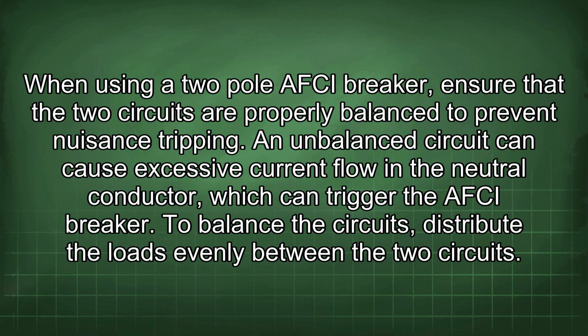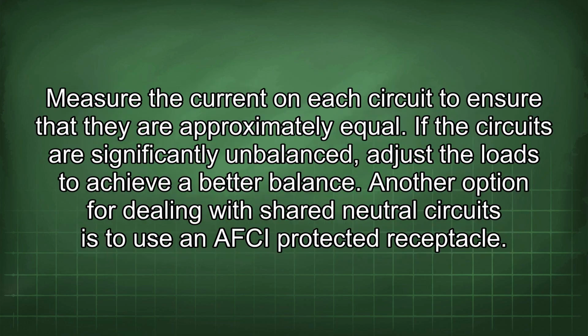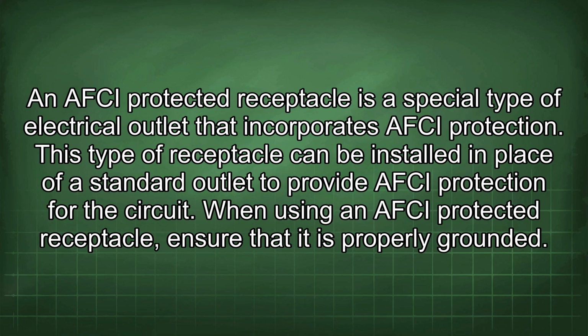To balance the circuits, distribute the loads evenly between the two circuits. Measure the current on each circuit to ensure that they are approximately equal. If the circuits are significantly unbalanced, adjust the loads to achieve a better balance. Another option for dealing with shared neutral circuits is to use an AFCI protected receptacle. An AFCI protected receptacle is a special type of electrical outlet that incorporates AFCI protection.